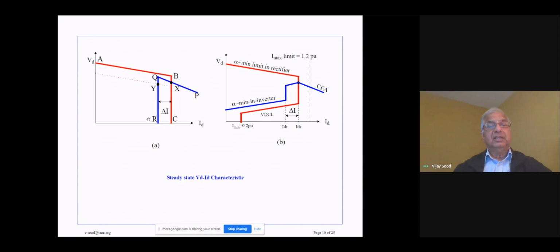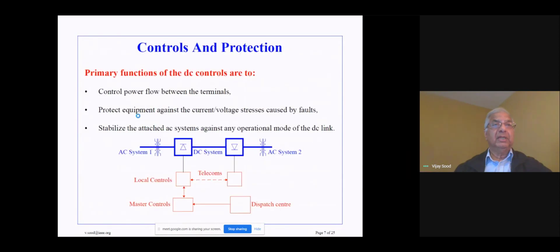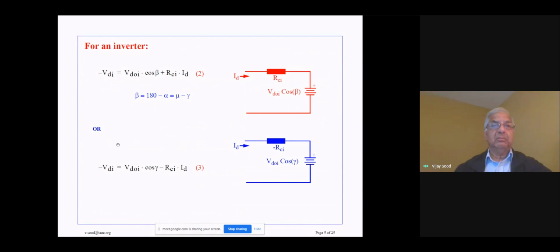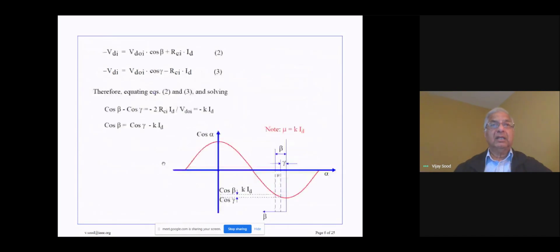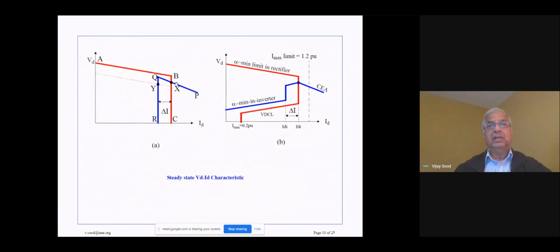Superimposed on this is the characteristic for the inverter. And you can see this line PQ. Line PQ represents the same kind of behavior, which is defined by equation number 3, with a negative slope, and the angle gamma defines a straight line with a different slope, and that is this line PQ. Again, to implement a constant current characteristic for the inverter side, we impose this line QR. So now you can see that the rectifier has this characteristic shown in red. The inverter has this characteristic shown in blue.